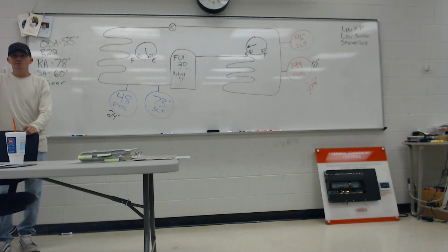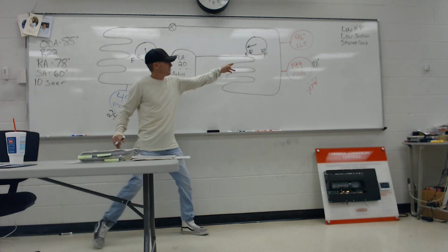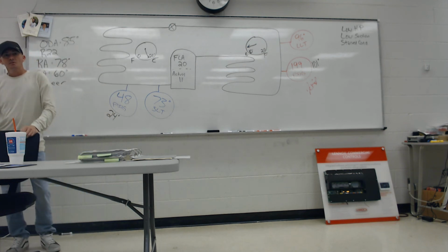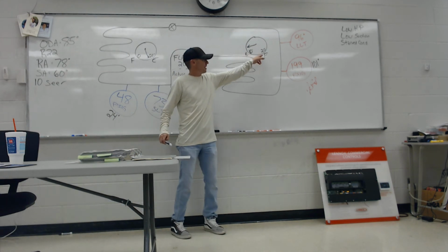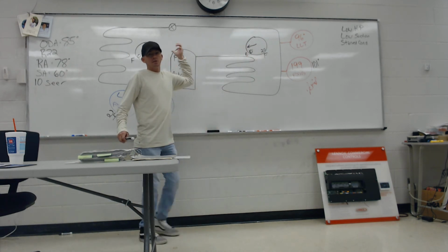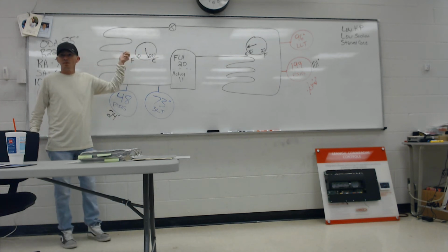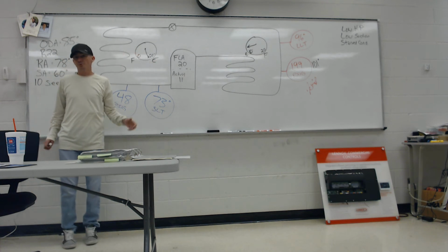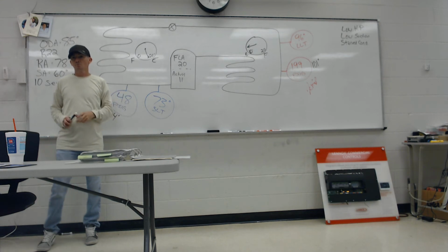You guys see how we did it? You like the little fuel gauges? Thank you, Roger Shepherd. Mr. Shepherd taught me that when I was a student here. Everybody see how we did that? On the condenser, it's normal: 0 is empty, a high number is full. Superheat on the evaporator is flip-flopped: a high number is empty, a low number is full. It's reverse acting on the evaporator side.